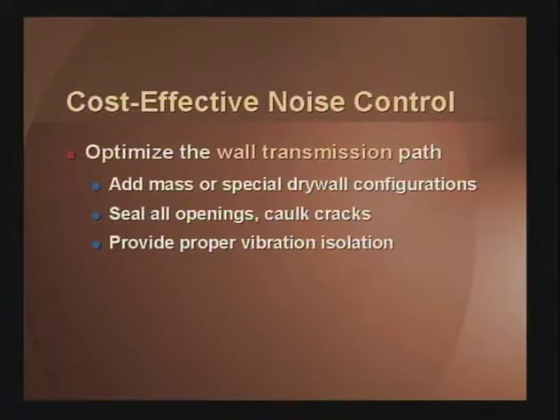Seal all the openings. Caulk the cracks. If you see any light through that wall at all, you're reducing the effectiveness of the barrier. And, of course, provide proper vibration isolation under the fans and moving components. Here's a picture of some of the different wall configurations you might encounter.